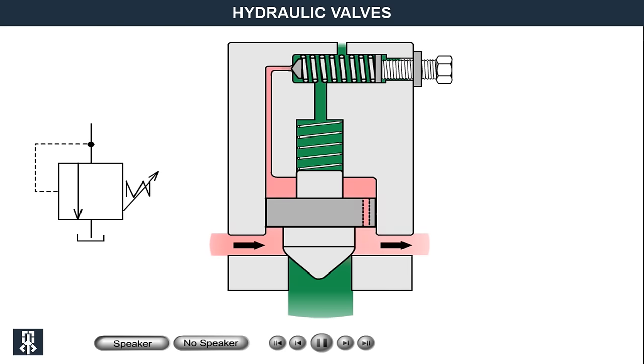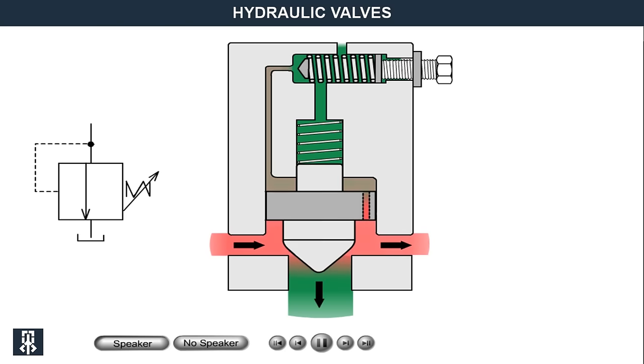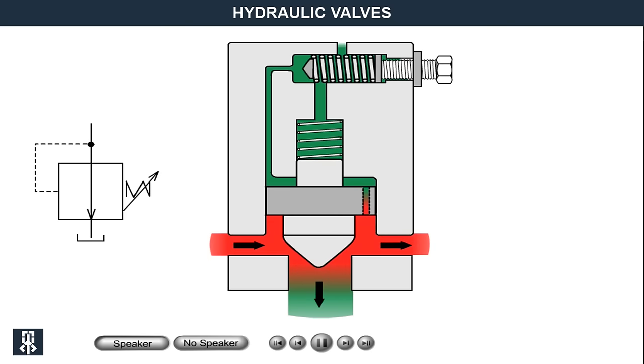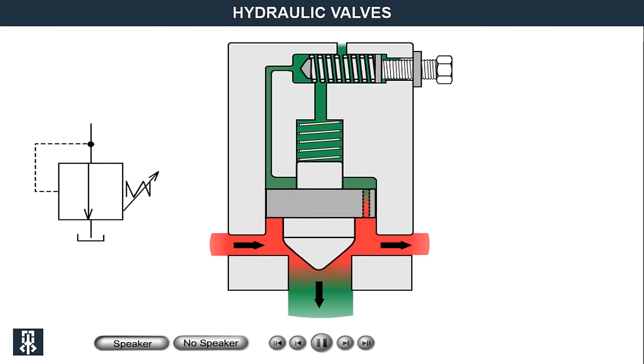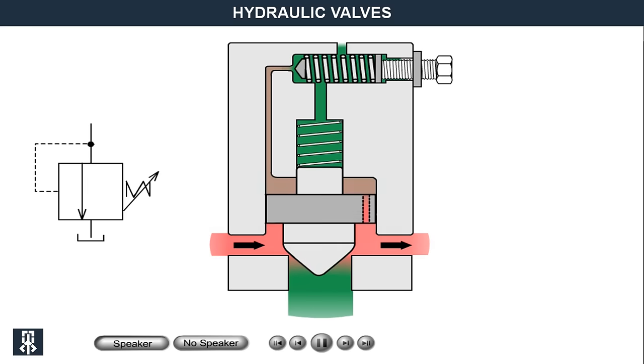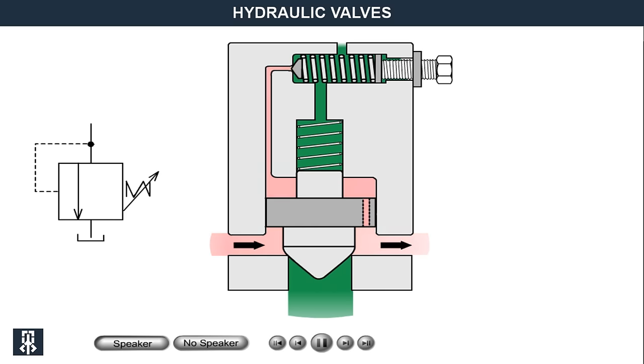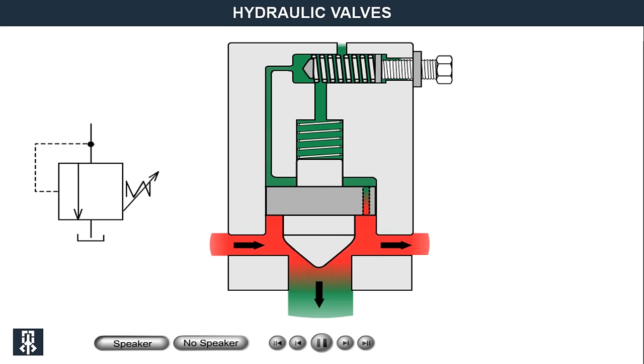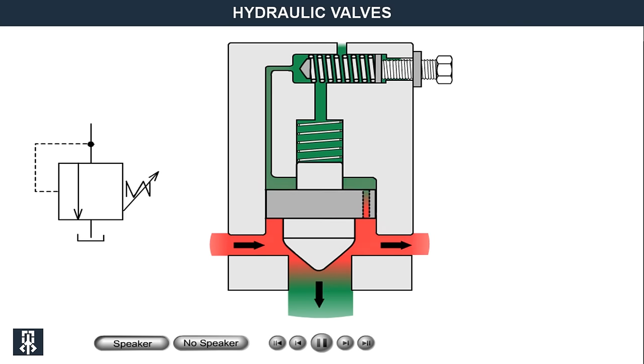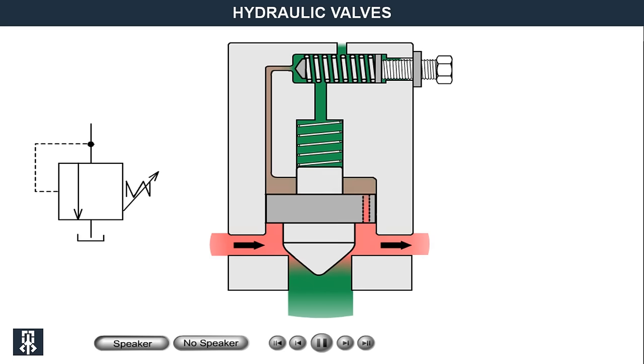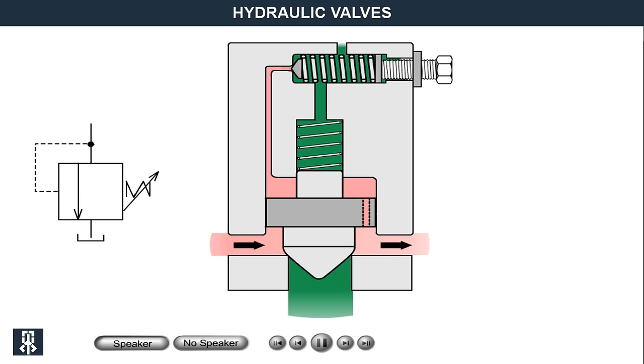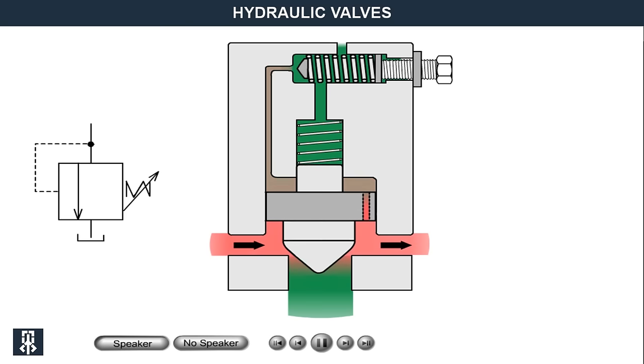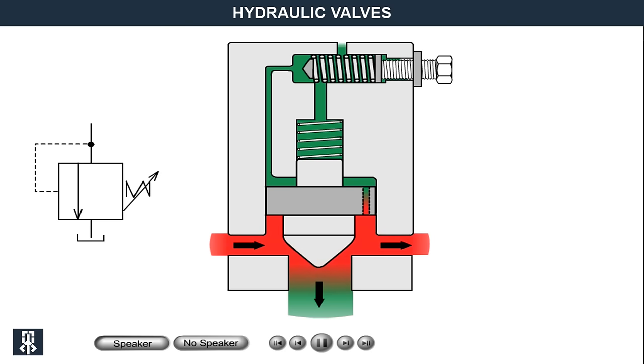A small spring-loaded pressure limiting valve is built in as a pilot valve in the main valve. A channel ensures that there is the same pressure on both sides of the large valve peg. When the pressure increases, it also increases against the pilot valve's peg. When the pressure on the pilot valve reaches opening pressure, the oil pressure drops on the main valve's rear area and it also opens after a moment. Since the opening pressure is in principle the same as the flow-through pressure, the valve can be set to the highest permissible for the system.